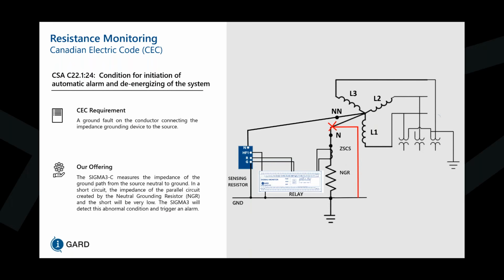Now, when we have a short circuit condition and we are not experiencing any current or voltage at the neutral, our high frequency signal comes along the path to the XO point and it goes down the shorted path to ground. So it doesn't experience the voltage drop across the resistor, and we get the full signal back to our relay. So when we get the full signal back without experiencing the voltage drop across the resistor, we can deduce that we're in a short circuit condition.